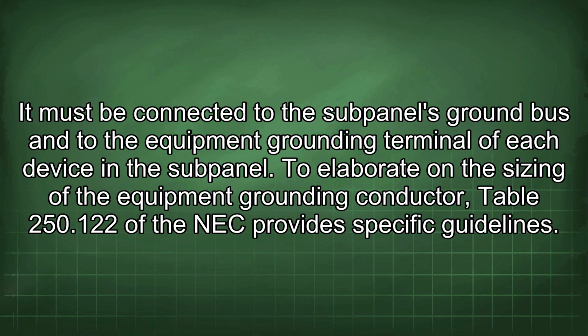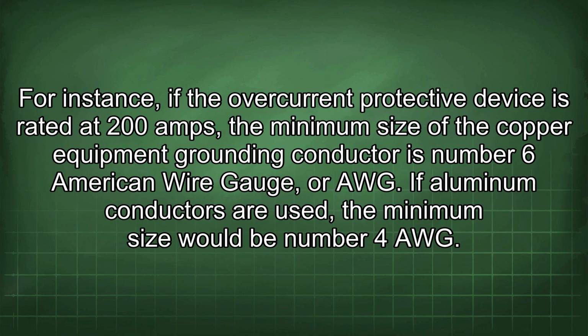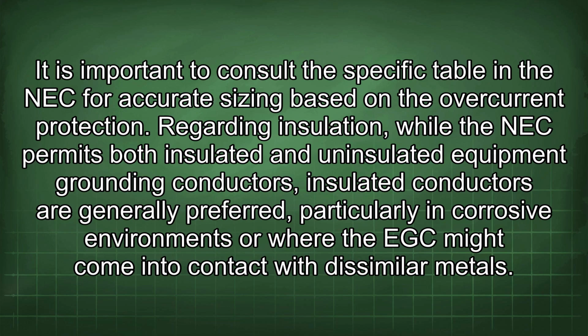To elaborate on the sizing of the equipment grounding conductor, Table 250.122 of the NEC provides specific guidelines. For instance, if the overcurrent protective device is rated at 200 amps, the minimum size of the copper equipment grounding conductor is number 6 American wire gauge, or AWG. If aluminum conductors are used, the minimum size would be number 4 AWG. It is important to consult the specific table in the NEC for accurate sizing based on the overcurrent protection.